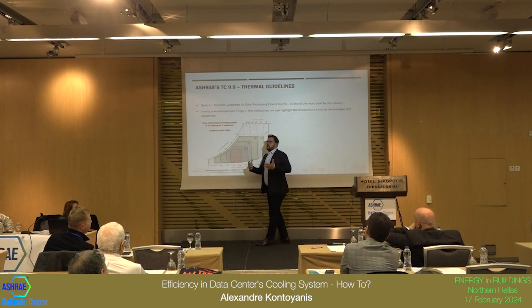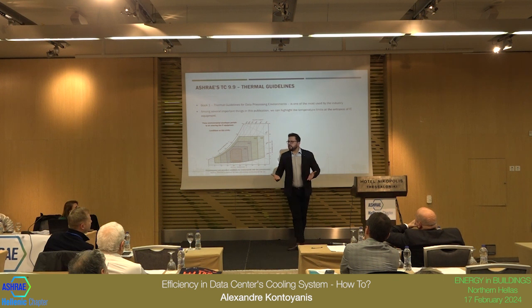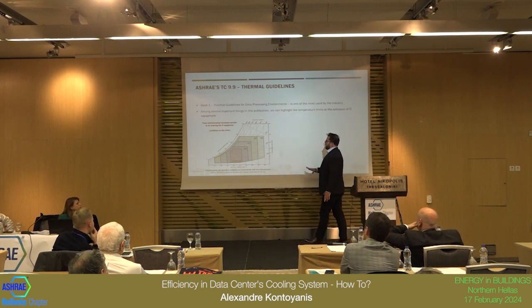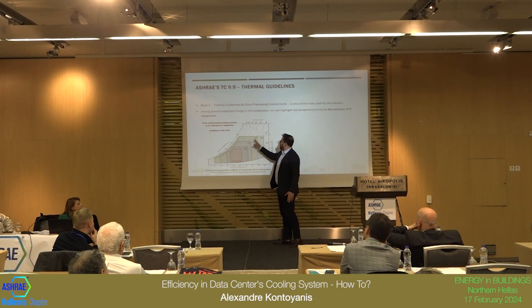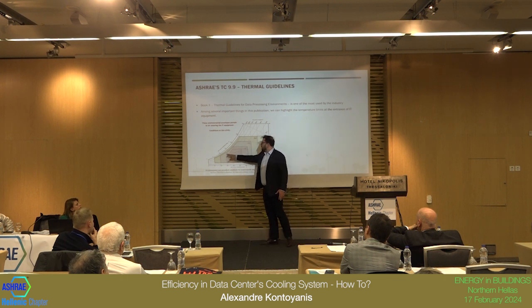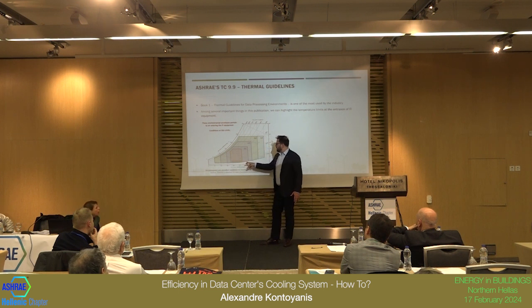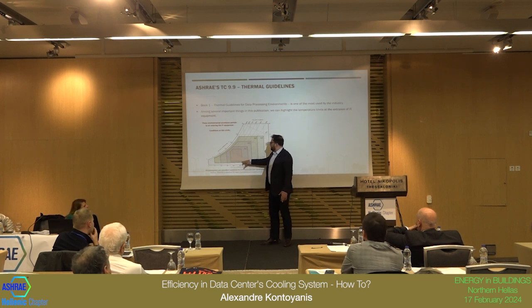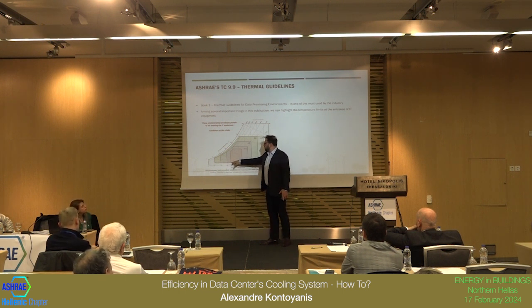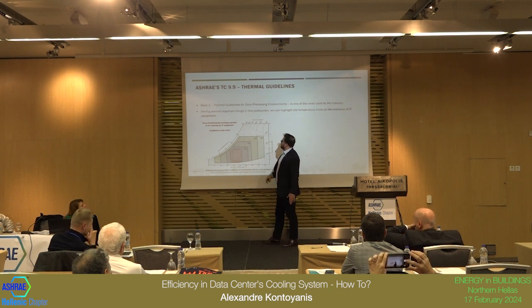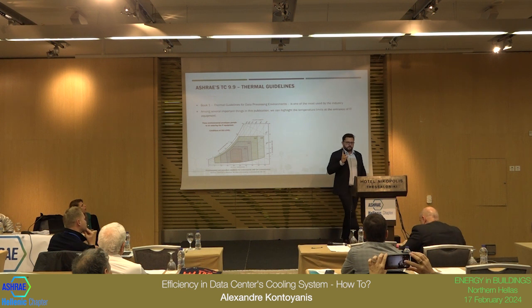This area is the balance between risks and efficiency. And you have those other areas, A1, A2, A3, A4, the allowable limits for each type of equipment. Data centers almost always work at A1. So we're talking about 18 to 27 degrees Celsius. Here it's -9 degrees dew point, around 9 to 12% relative humidity. Here, 15 degrees Celsius dew point, and here, 70% relative humidity.